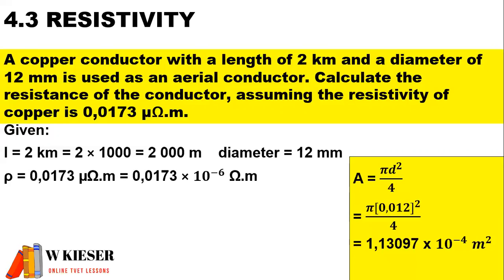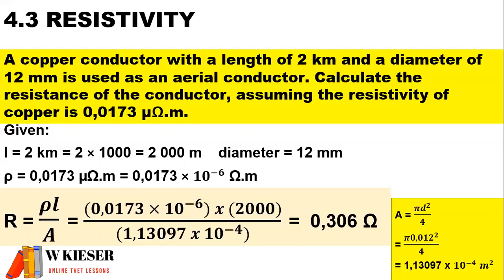To calculate the cross-sectional area, we use the formula pi d squared over 4. The diameter needs to be in meters, so we convert 12 millimeters by dividing by 1,000. Inside our formula it will be pi multiplied by 0.012 squared, divided by 4, in order to get the cross-sectional area in meters squared. Once we substitute all those values to calculate the resistance, the resistivity is 0.0173 times 10 to the power of minus 6, the length of the conductor is 2,000 meters, and the cross-sectional area is 1.13097 times 10 to the power of minus 4. Therefore, the resistance of the conductor is 0.306 ohms.